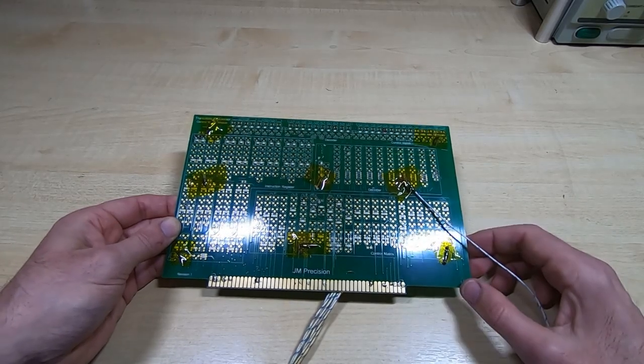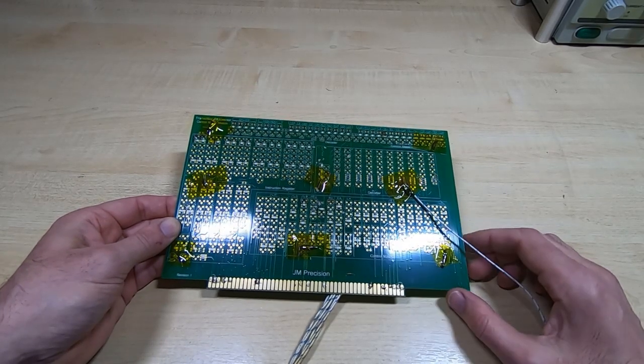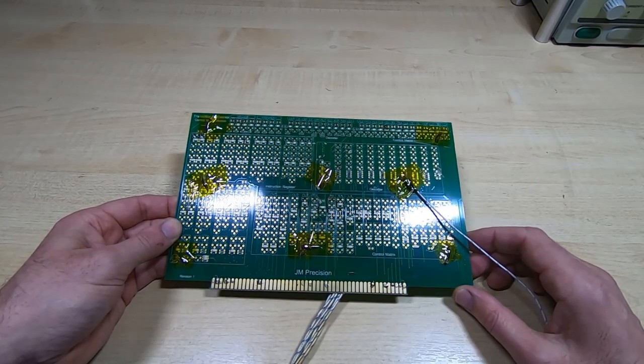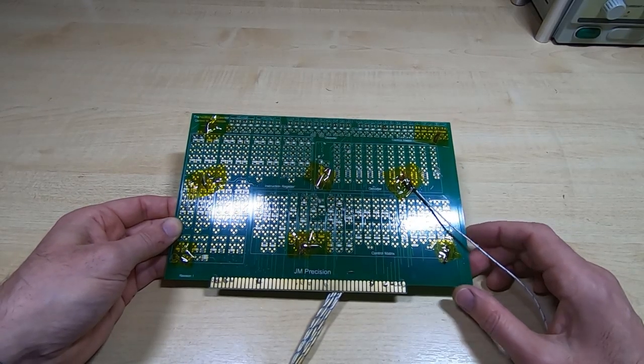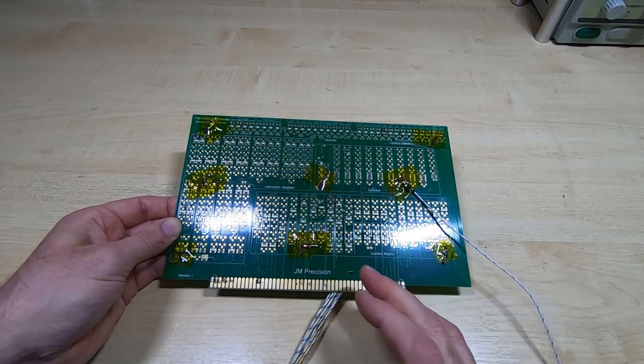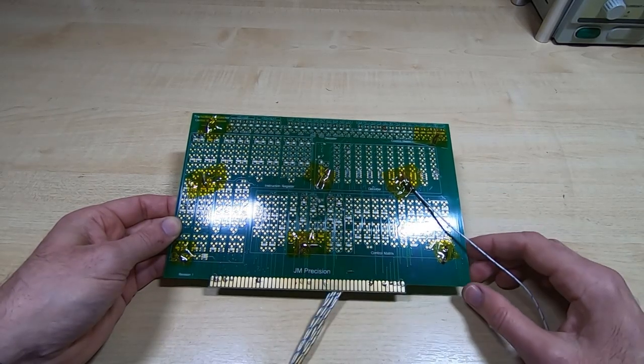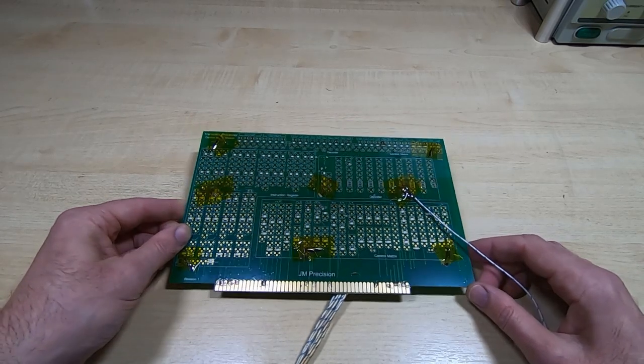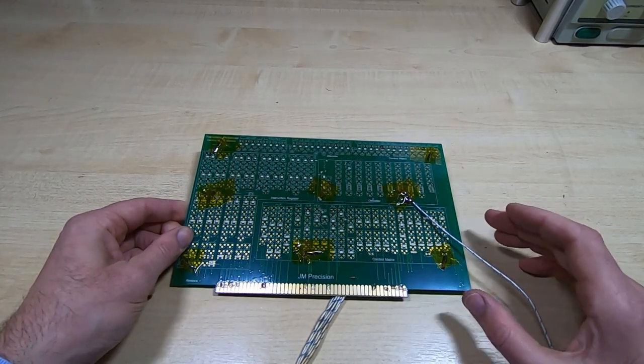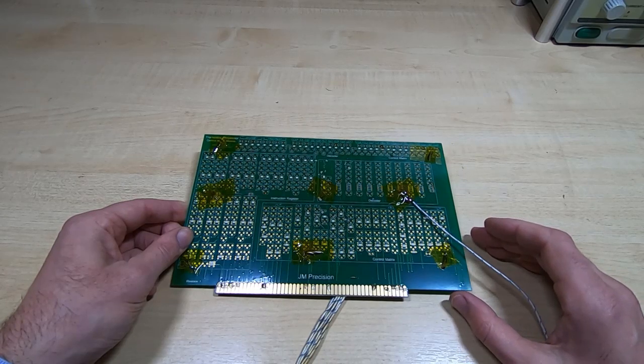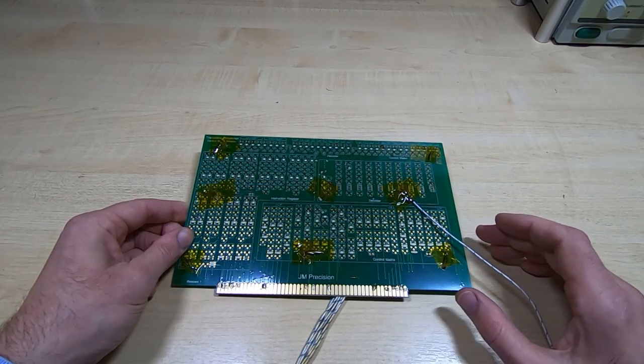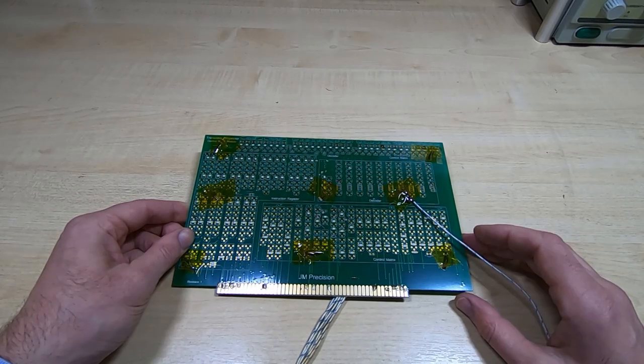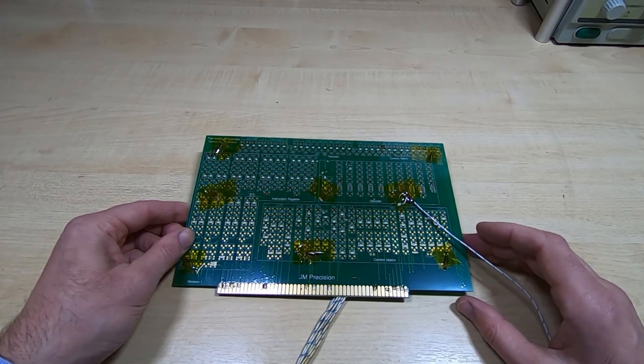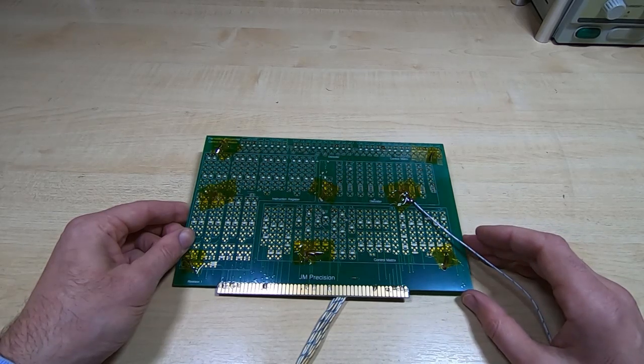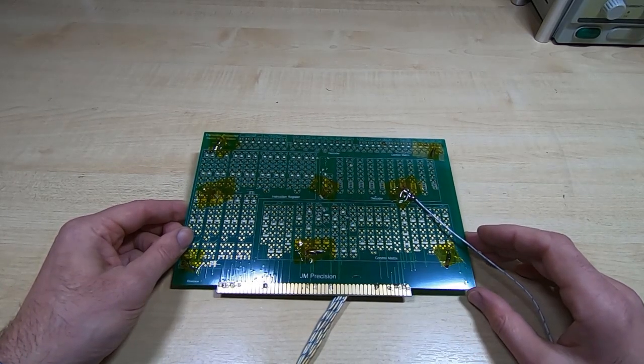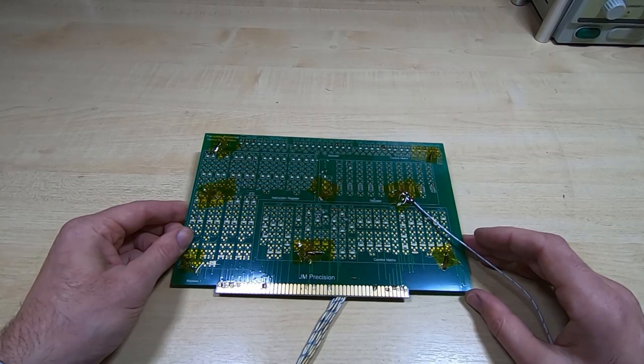So the way I go about doing this, and there are many ways you could do this, of course, but I've developed a methodology over the years that I tend to follow. I will initially calibrate the probes over the range I intend to use them for the project. What I will then do is periodically recalibrate them or recheck them through the project. And when I say recalibrate, I don't mean adjust them. If they've gone out of adjustment, then really I've got to start the process again. They shouldn't really change, and if they do, chances are one was faulty or is failing. It's just really to revalidate them.